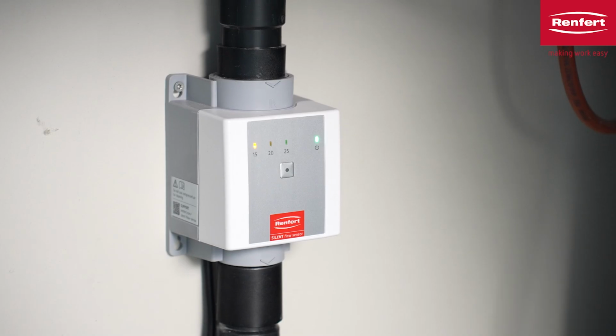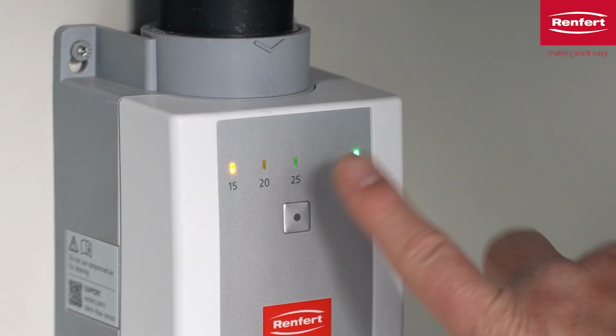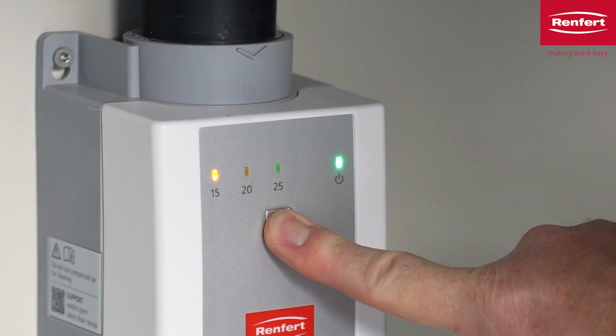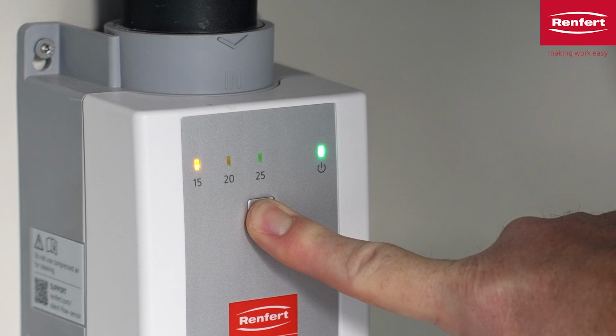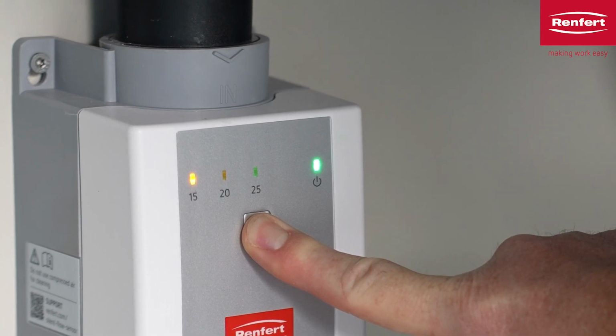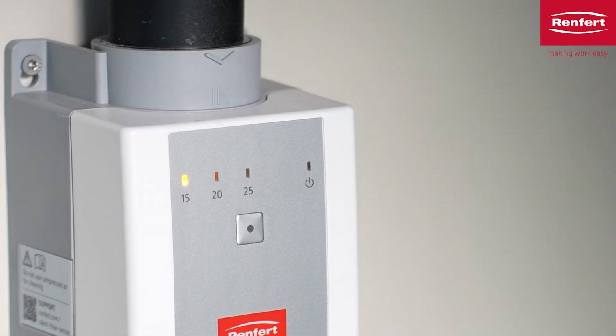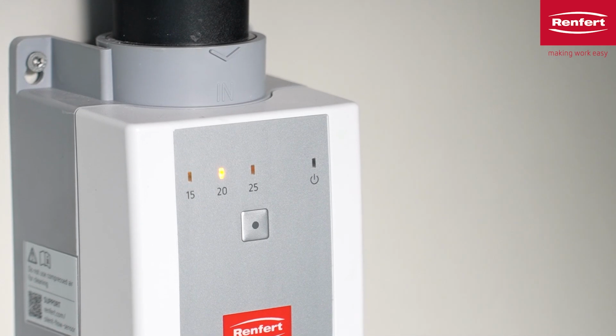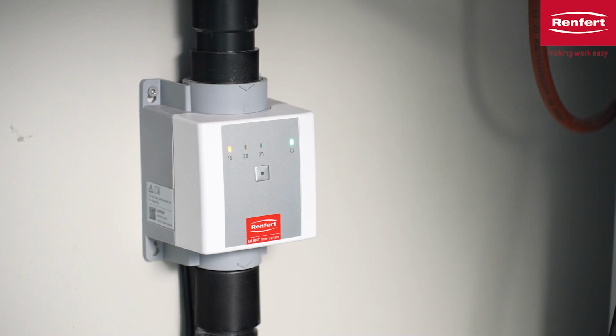Press the button for approximately 5 seconds. After approximately 2 seconds, a single acoustic signal sounds for setting the warning threshold. Continue to hold down the button. After approximately 5 seconds, a double acoustic signal sounds to perform the zero adjustment.